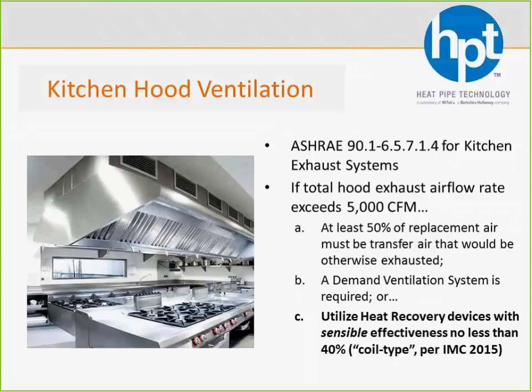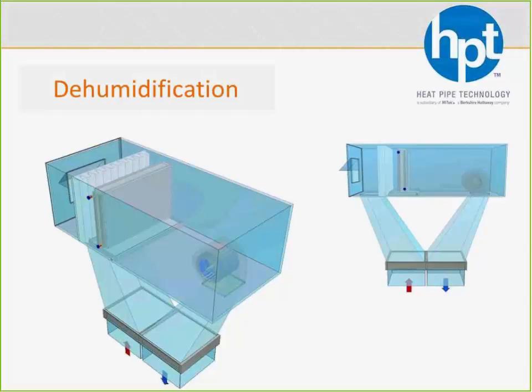Yeah, they've got to do a little bit more cleaning than usual, but it's going to save them some energy and help them meet code. And lastly, another cool thing you can do, if you're familiar with the wraparound heat pipe, its sole purpose is for dehumidification, but that's for next month. But the HRM can be used for dehumidification as well. In this case, we're actually wrapping around the air, so to speak.